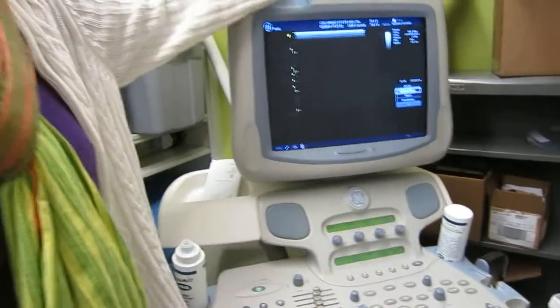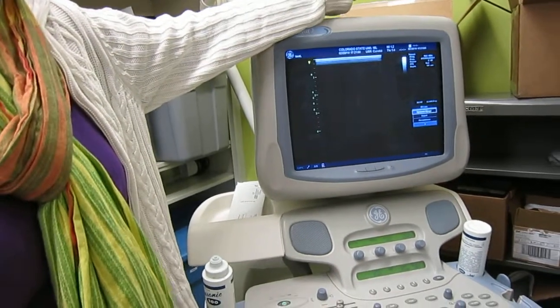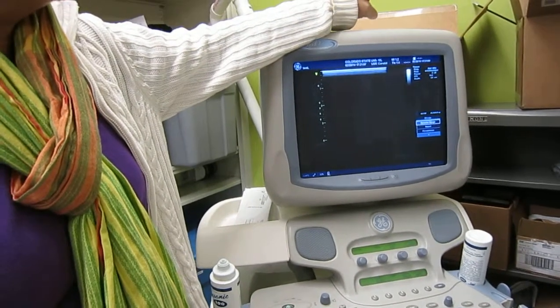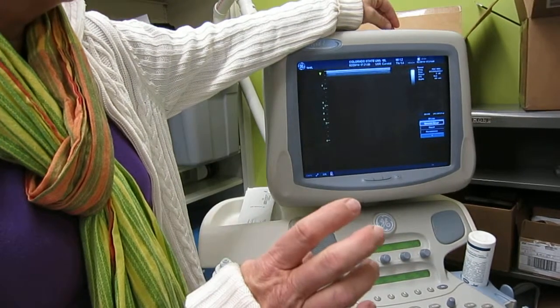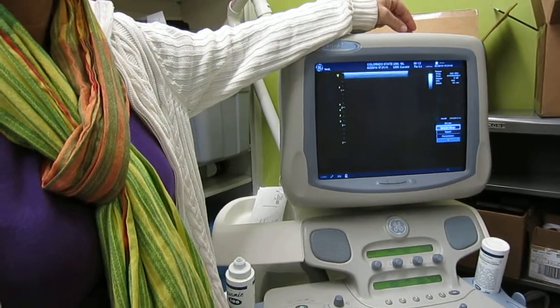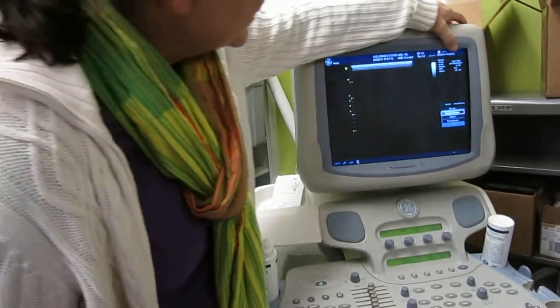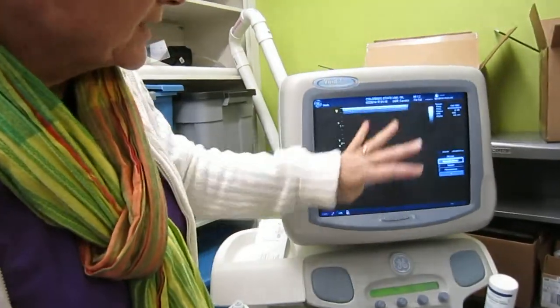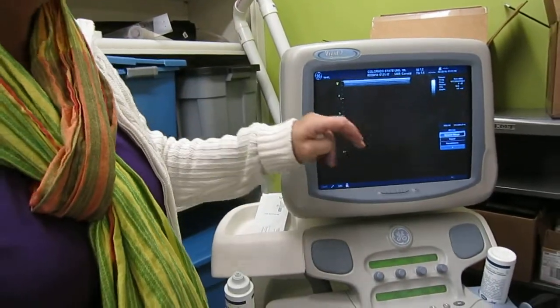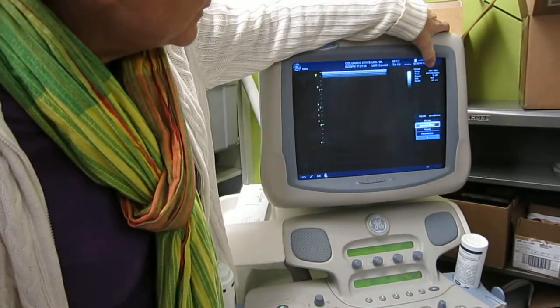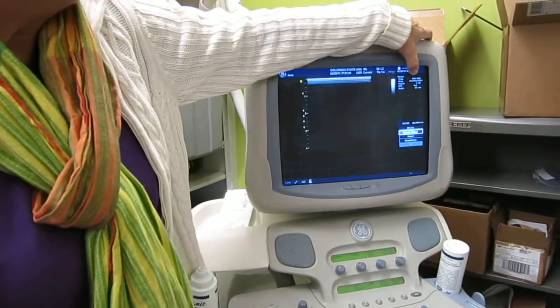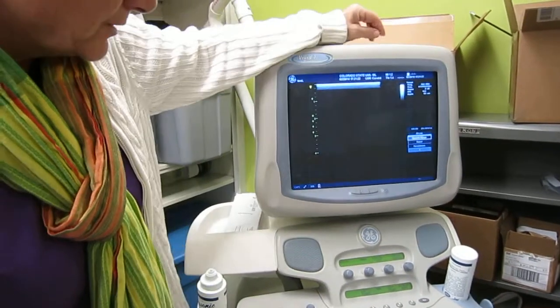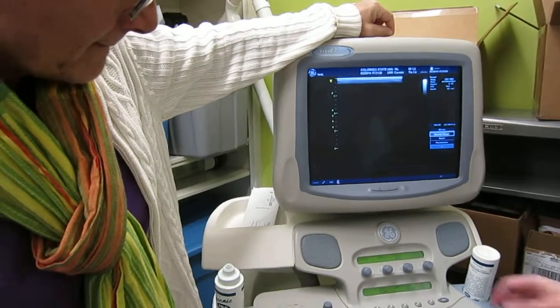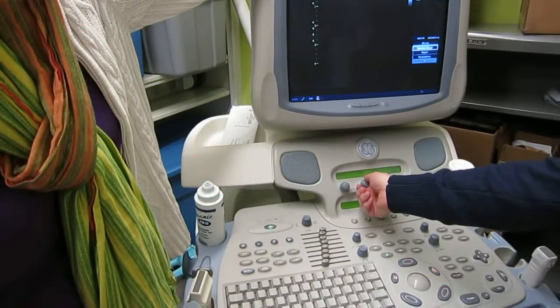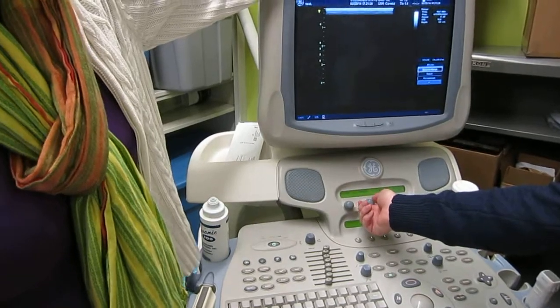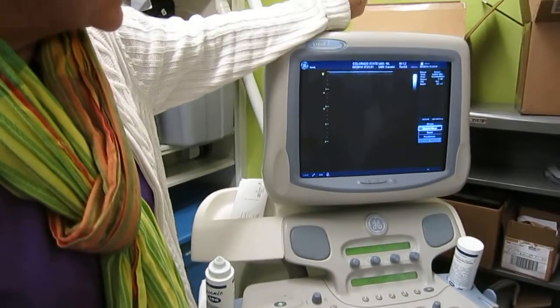So if you're actually scanning and you say, this is as pretty as I've gotten, I really like these settings, you can create that. Yep, the preset actually defaults to certain frequencies, certain gain, brightness settings and things like that, okay? So this one defaulted to 10 megahertz. So how do you change the frequency on that to see where a range is? Oh, it's a straight 10. Okay, that's the frequency then.